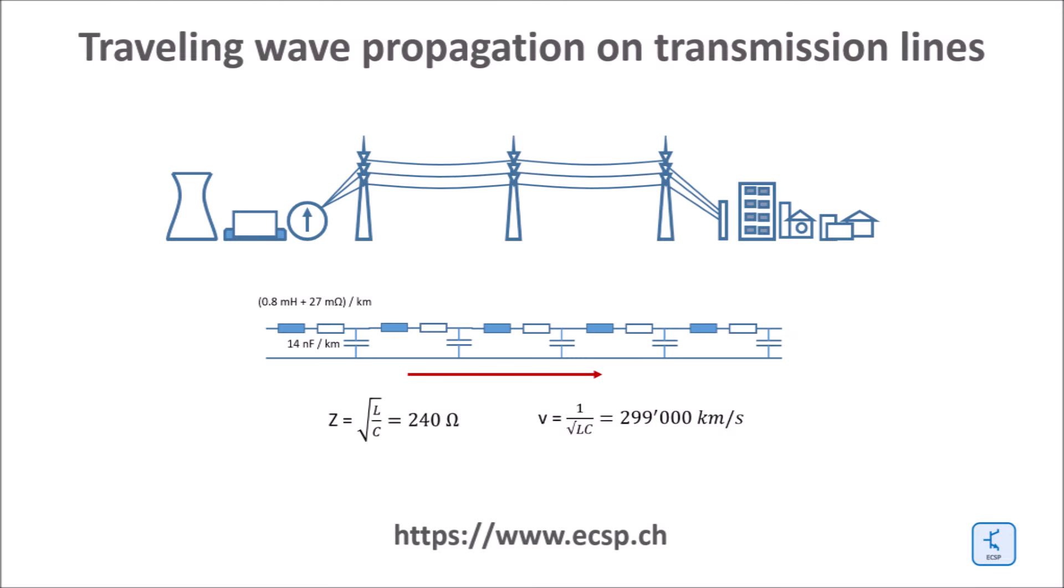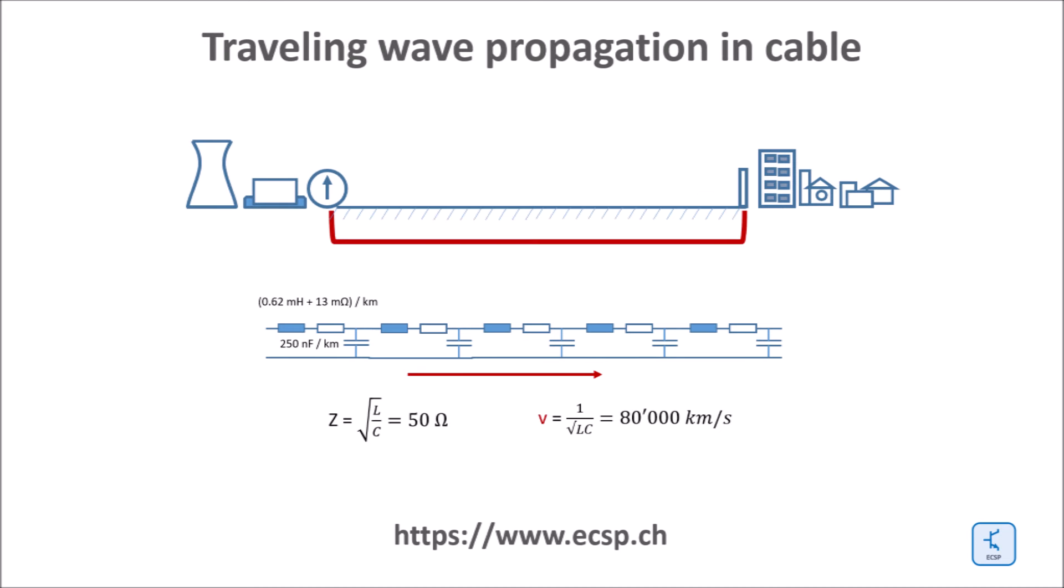There are two most relevant line parameters to be considered. The first one is the surge impedance and the second one is the propagation speed. The wave propagation speed on overhead lines is typically very close to the speed of light. In cable however, the propagation speed is around 30 percent of the speed of light due to the dielectric constant of the cable insulation.